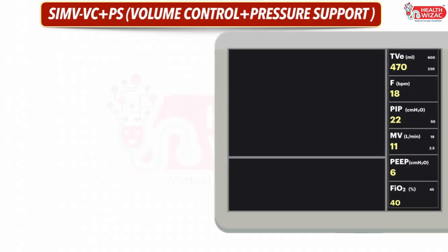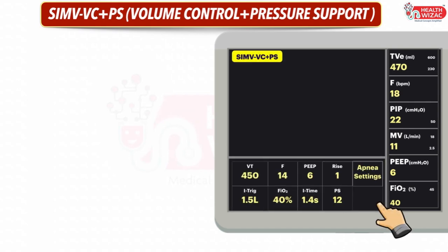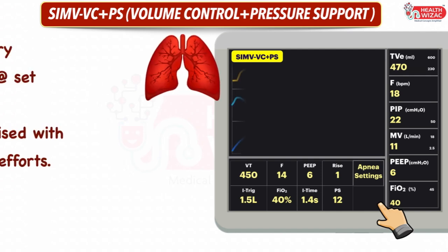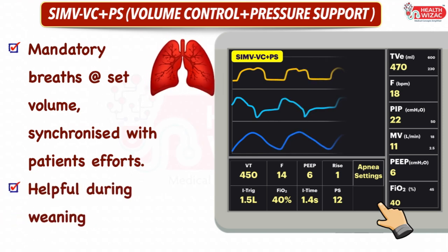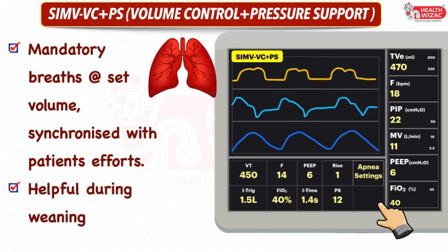Next is SIMV volume control plus pressure support mode. In this mode we have to set tidal volume, frequency, PEEP, rise time, inspiratory trigger, FiO2, inspiratory time, pressure support settings, and apnea settings for backup ventilation. In this mode, the ventilator provides mandatory breaths at set volume which are synchronized with the patient's spontaneous efforts.